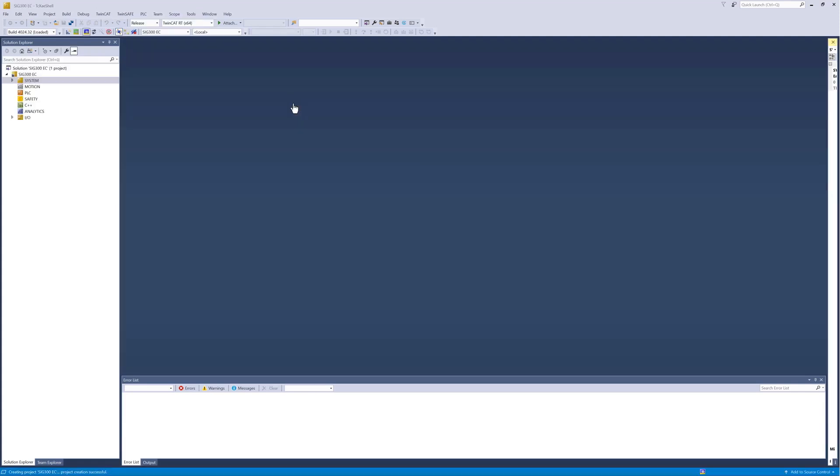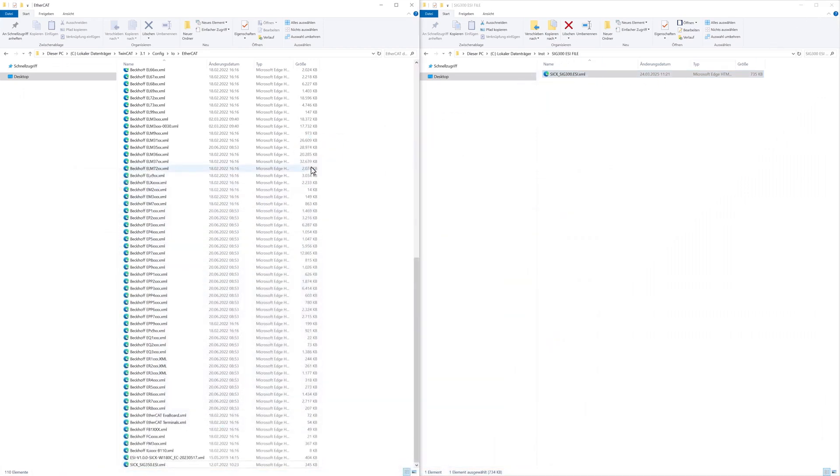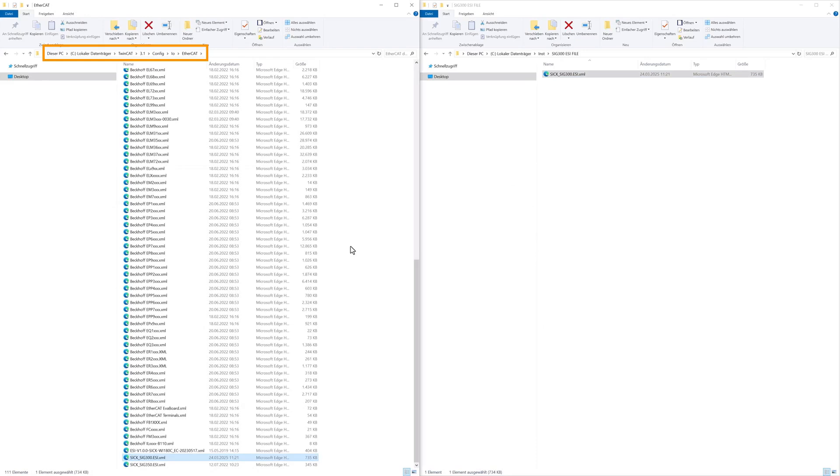In order to integrate the SIG300 into the EtherCAT network, the EtherCAT device description file, ESI, must be copied to a specific location in the TwinCAT installation directory. The path for a standard installation is C TwinCAT 3.1, config IO EtherCAT.